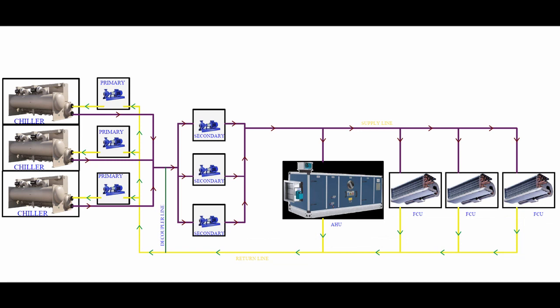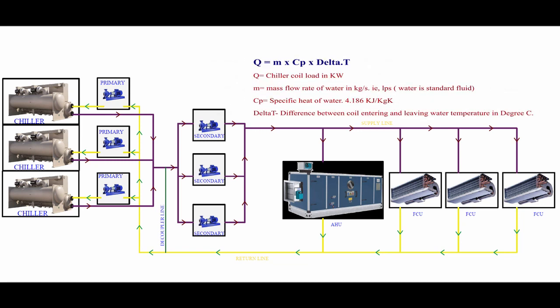Before going to the explanation, we should calculate how much chilled water flow rate is required through each equipment. Say, each chiller is having a cooling capacity of 200 tons of refrigeration. We can calculate the flow rate using the equation Q = M × Cp × ΔT. Here, Q is the chiller coil load in kilowatt. If it is 200 tons of refrigeration, you can convert tons of refrigeration to kilowatt by multiplying 3.516. So 200 × 3.516, you will get around 703.2 kilowatt.